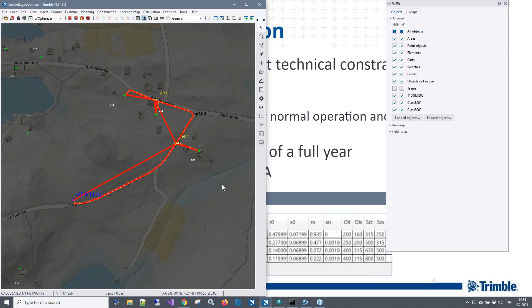In addition, Trimble Optimizer has short circuit calculation, which is needed primarily for the minimum one-phase short circuit requirement enforcing, and also it is needed for the fuse planning, where we are guaranteeing that the safety requirements are being fulfilled, and in addition we are aiming for a good selectivity. So we can take a look from here how it looks.